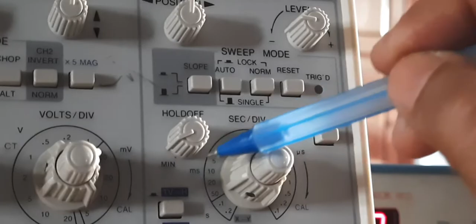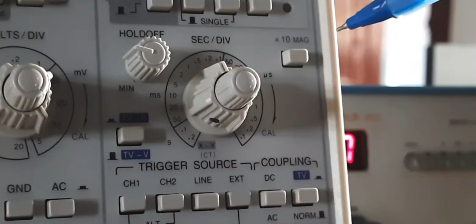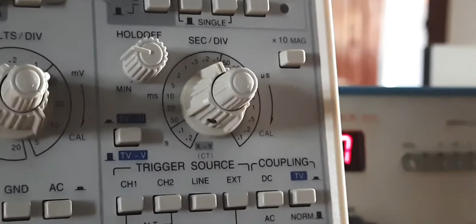Then coming to hold, we discussed minimum and maximum. Using this you can hold the AC signal that is moving into a stationary position. Then this is times per division into 10 magnification. That is what you will be seeing, into 10 magnification, if you press this. If you release this, no multiplication factor will be provided. Usually see to it that this is in the released position. Unless there is no choice, then press this button. Usually you will not need it for your usual lab range of frequencies.